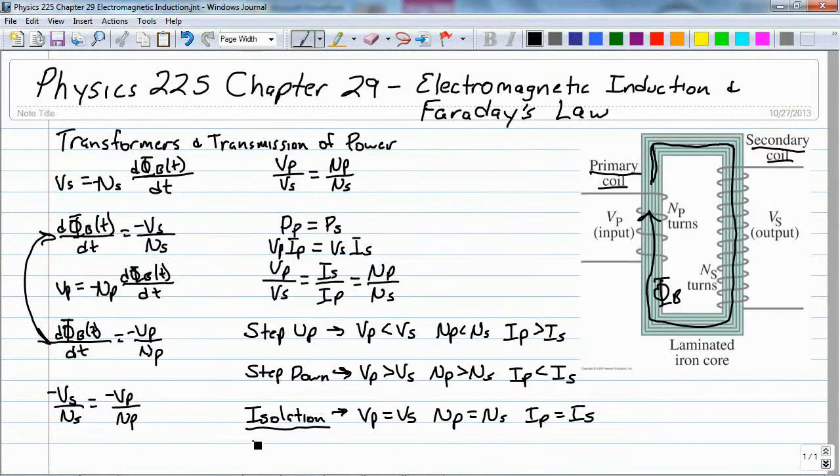You'll find that they're used in the medical field quite a bit, because by law you can't hook somebody directly to a piece of electrical machinery. If something were to happen, the isolation transformer would, in a sense, isolate the patient from the device. And these isolation transformers can be made so that they disconnect if something were to go wrong with the equipment.